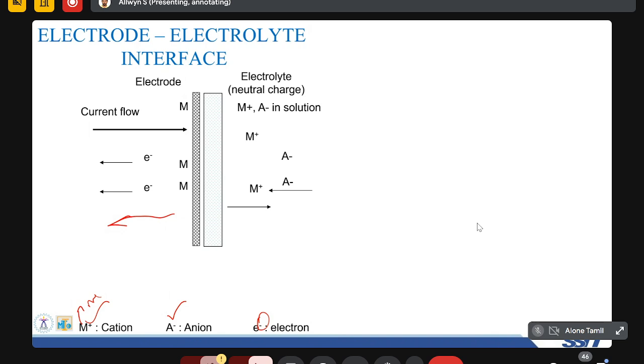Yeah. So why it is most important is that there is something called the charge double layer and polarization. So in order to measure any biosignal, the electrode should be a non-polarized electrode, which means it should not be capacitance based. So usually the electrode has an impedance and it has a capacitor. So if there's a charge double layer, it blocks the amount of charge that flows through. So it's a polarized electrode. Okay. For measuring any biosignal, we have to use a non-polarized electrode. By analogy, a non-polarized electrode acts as a resistor. However, a polarized electrode is like a capacitor. So it stores charges and doesn't allow them to flow through.